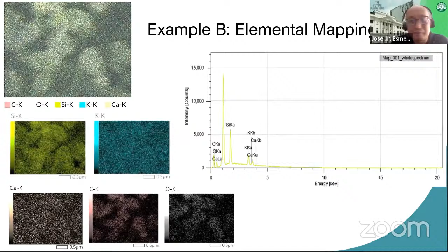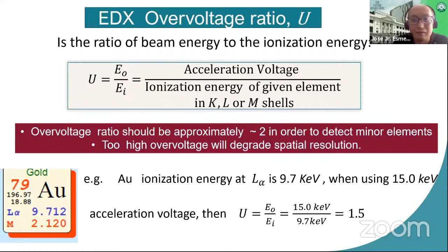EDX needs what you call overvoltage. Overvoltage is the ratio of beam energy to ionization energy. That means you need to use a higher acceleration voltage in order to identify more elements. In practice, the ratio should be 2 in order to detect minor elements. A higher overvoltage, I mean 3 or 4, will degrade the spatial resolution. As an example, in the table, gold has an ionization energy of 9.7 kilovolts. If I use 15 kilovolts acceleration voltage, that's enough, a ratio of about 1.5. If I want to get more details, I use 20 kV to approach 2.